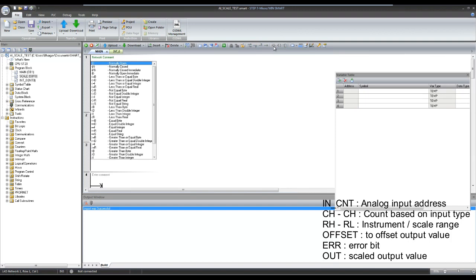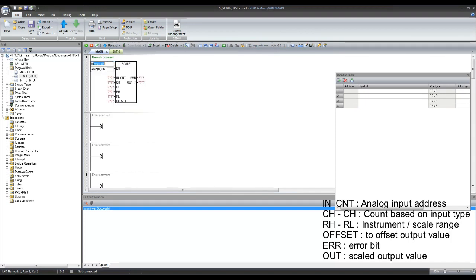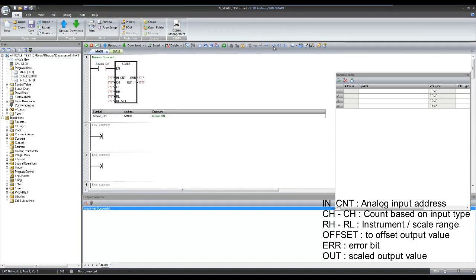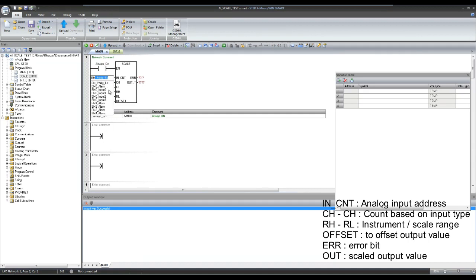I am configuring this block for analog input channel 0 for 4 to 20 milliamps input and scaling it between 0 to 100 range.